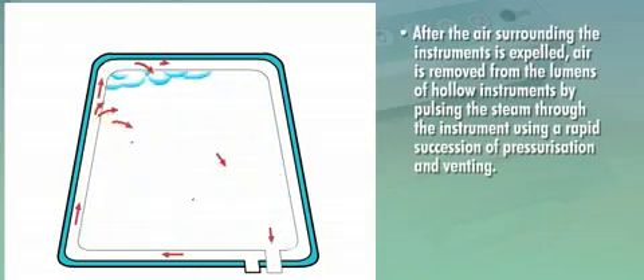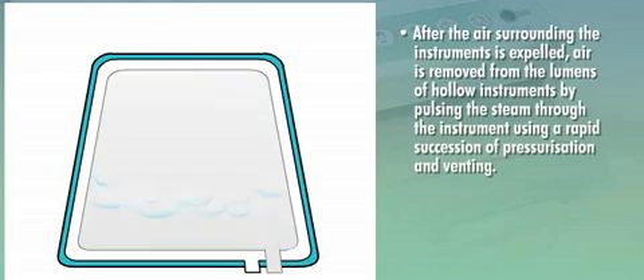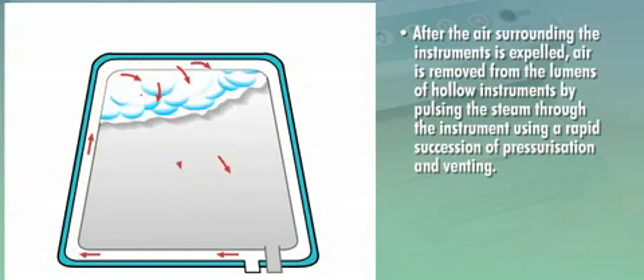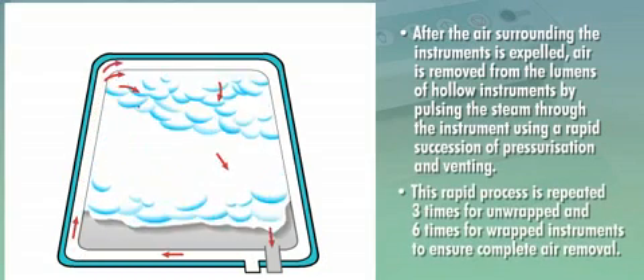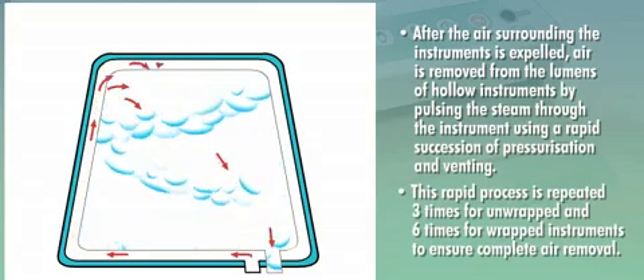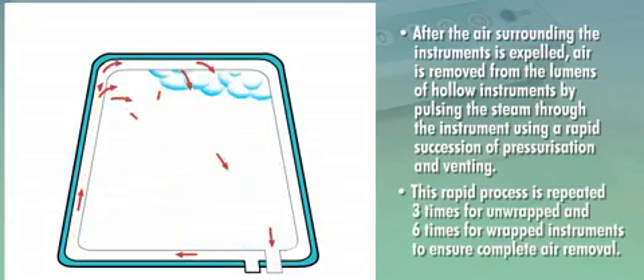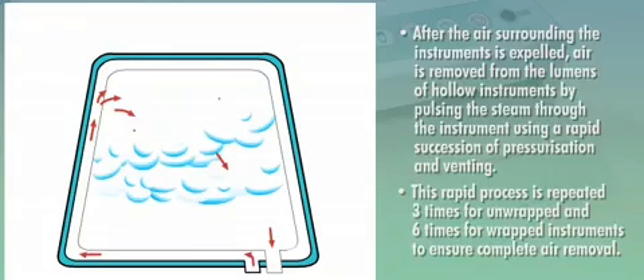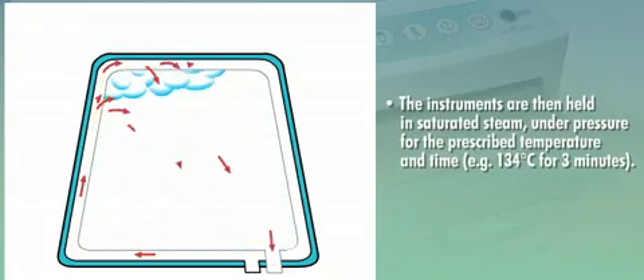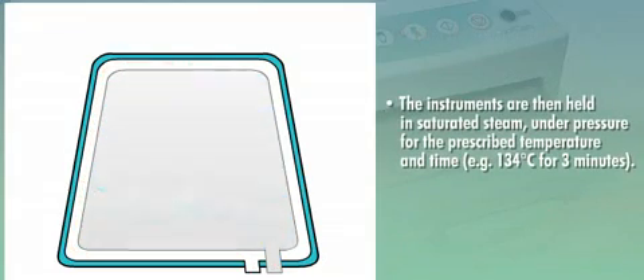After the air surrounding the instruments is expelled, air is removed from the lumens of hollow instruments by pulsing the steam through the instrument using a rapid succession of pressurization and venting. This rapid process is repeated 3 times for unwrapped and 6 times for wrapped instruments to ensure complete air removal. The instruments are then held in saturated steam under pressure for the prescribed temperature and time, for example, 134 degrees Celsius for 3 minutes.